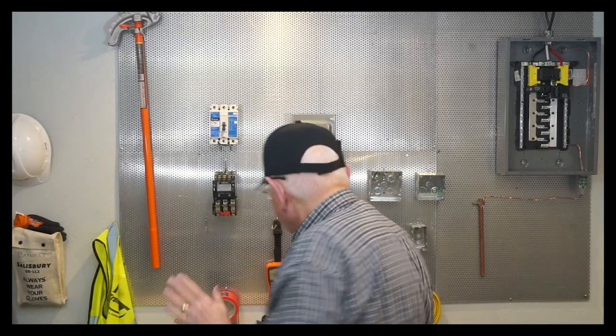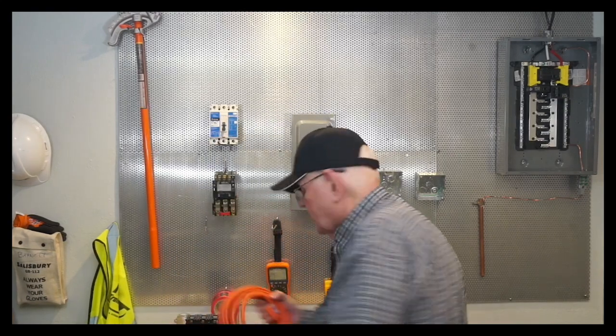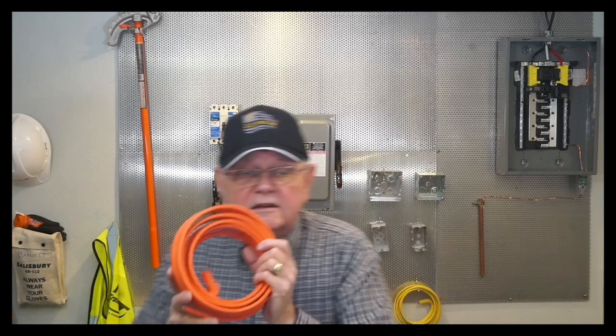Now, if we look, here's some type NMB cable, right? We know from the color coding this is going to be number 10. This is type NM non-metallic sheath cable, type B, and suitable only for dry locations and so forth. If it's NMC cable, that means the outer jacket is corrosion resistant.